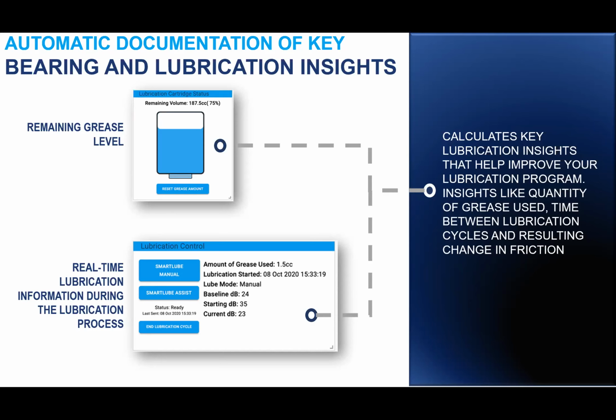So I ended up having to do a PM on a system that was designed to eliminate the PM to lubricate. So what we found was they would run empty, or they would fall off or get disconnected, and they thought they were lubricating and they were not. So the first thing we did is we control every movement, and we know the real-time feedback from that system.